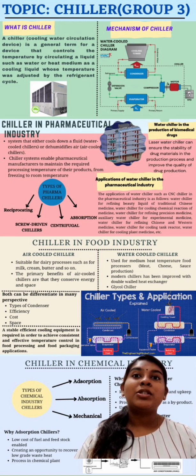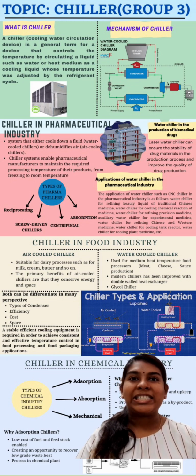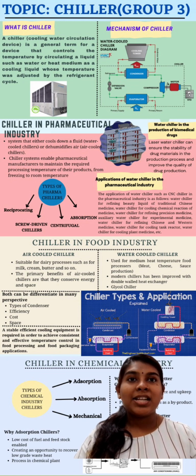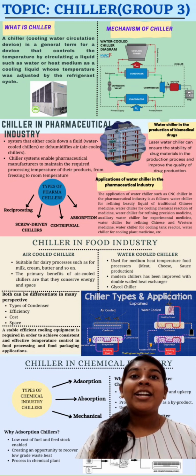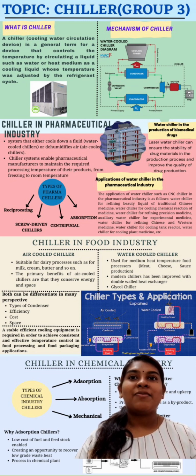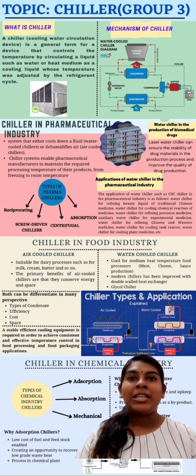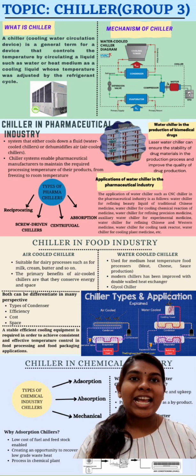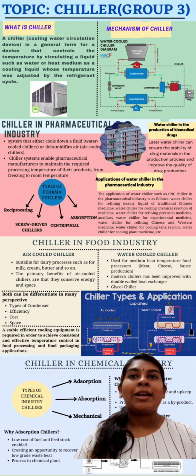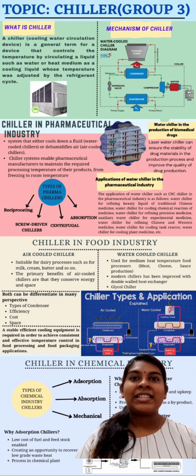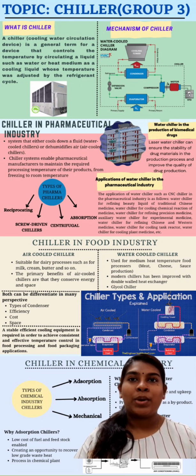Water-cooled chillers are used for medium temperature food processes such as cheese, meat and sauce production. As technology advances, different kinds of water-cooled chillers have been introduced, where modern chillers have been improved with a double-walled heat exchanger to prevent contamination. Chillers that use a medium of glycol are another example. As glycol is mixed with water, it functions as an antifreeze and assists in lowering the freezing point below that of water.